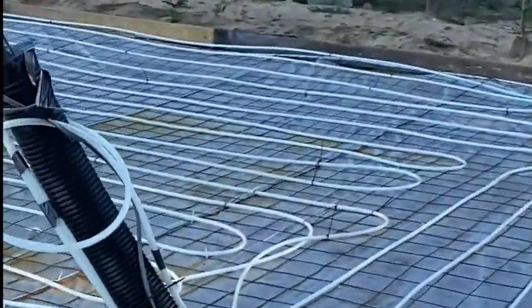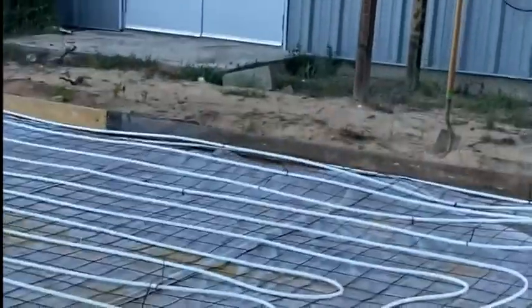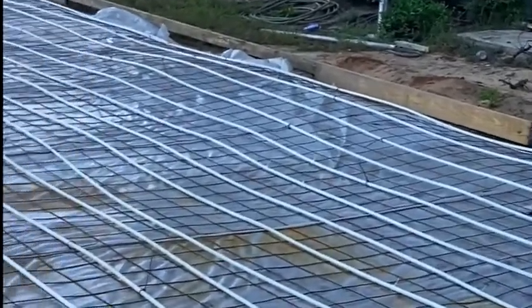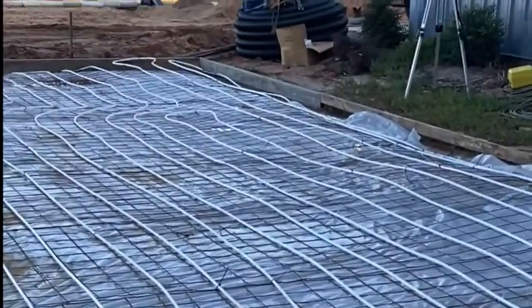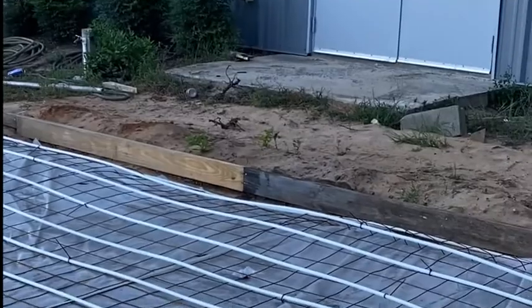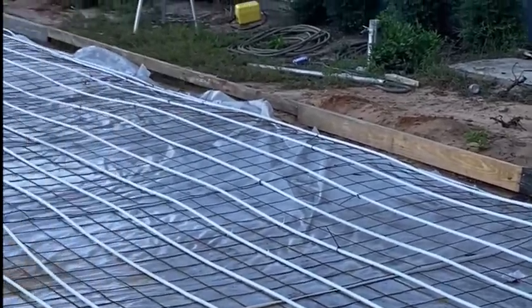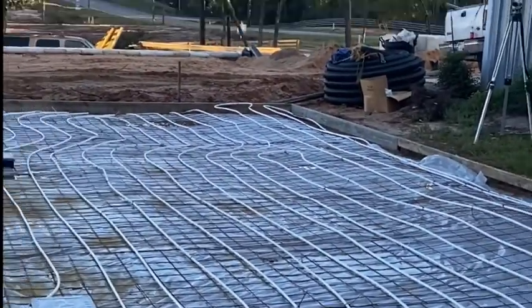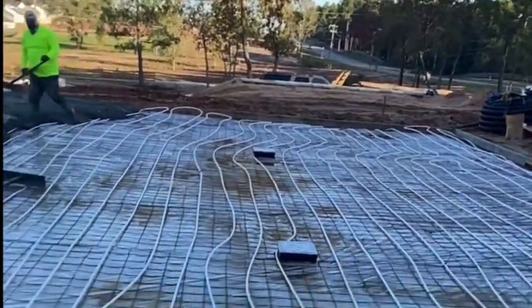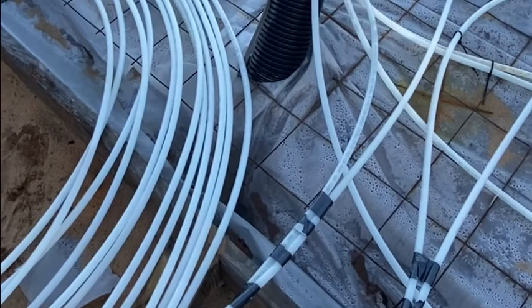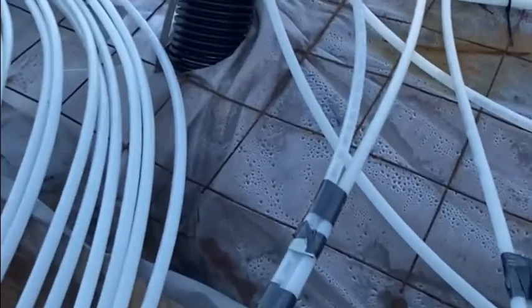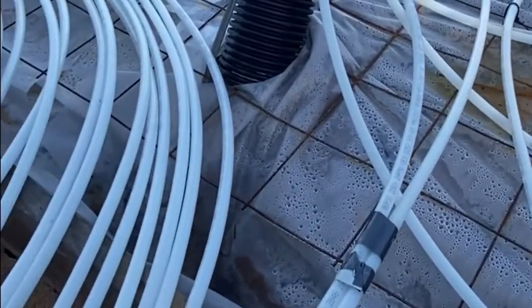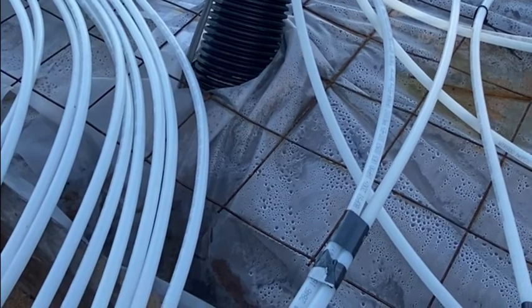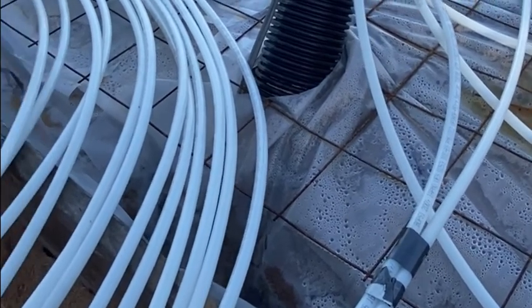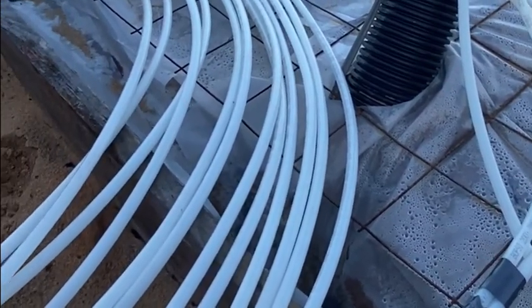We bought them in 300-foot rolls, because that's as far as you want to go with half inch pipe before you lose too much heat. So you can see we'd run the 300 feet out and then go right back here to the main area where the pumps, mixing valves, thermostats, and all our main controls come back here to the back of the greenhouse.